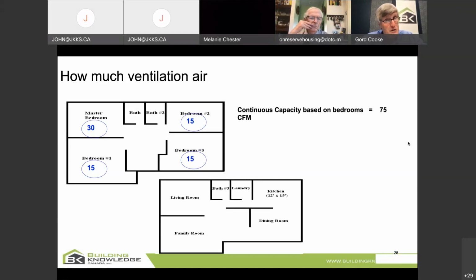Some of your communities, you would say, no, we have higher occupancy. That's fine. You simply count the number of people and you multiply by 15 cubic feet per minute. Think of it as basketballs of air. Every person in schools, it's 15 to 20 CFM. In offices, it's 15 to 20 CFM. In houses, it's 15 CFM per person. So that's how much air you need on a daily basis.